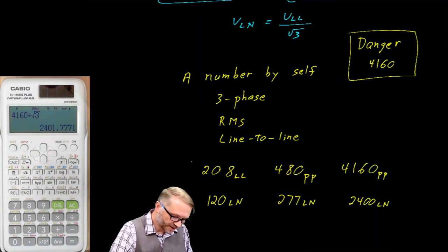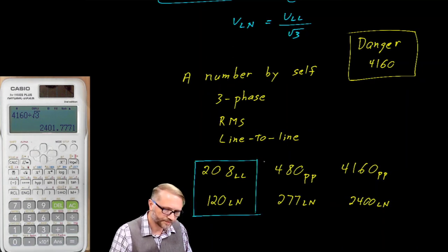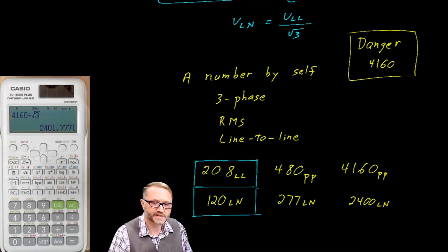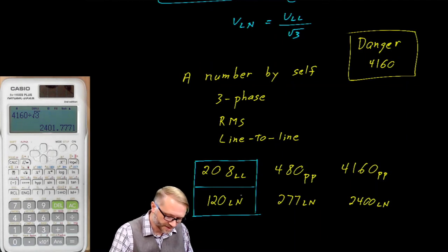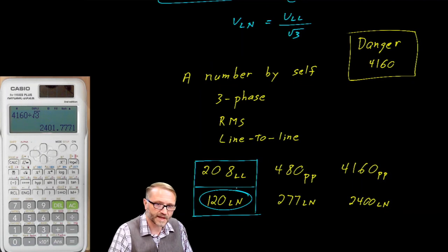Here's a parting thought: if you are in a commercial building, chances are very high that you are fed with a 208 line-to-line system. The outlet powering your computer is probably fed by one phase from that 208 going to neutral — that's 120 volts. The 480-volt system would be running the pumps and blowers that support the building.